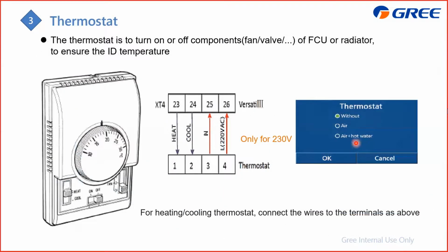And next is the thermostat, which turns the VERSATI on or off. After you connect the wiring, which is to connect the thermostat to the VERSATI, on the controller you also need to choose how to control it. Here, air means this thermostat controls the air conditioning. And next is air conditioning plus domestic hot water. For this one, we use the thermostat to turn the VERSATI on or off, and based on the priority selected for the hot water, we will turn it on and off.